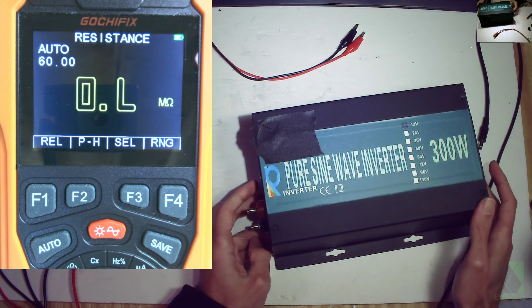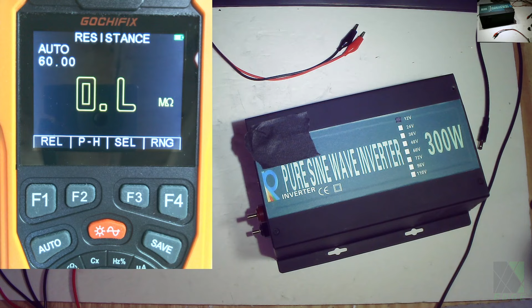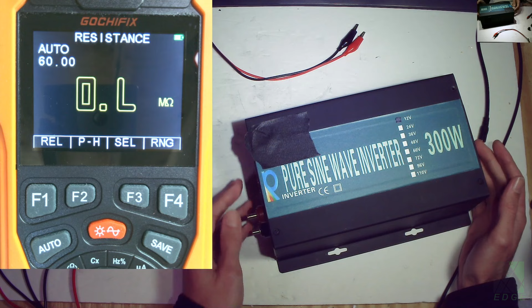If you probe the input of the inverter and you see an actual measurement, what you're looking for is you want to see hundreds of ohms, you want to see thousands of ohms, maybe hundreds of thousands of ohms, and you also want to see that reading starting to climb upwards because that would just indicate you're charging the capacitors on the input, and that's a pretty normal reading. That's nothing to be concerned about. It means the input is probably okay. It's probably not shorted. It's certainly not a guarantee of anything, but it does give you some information without actually opening the inverter and without spending a whole lot of time.